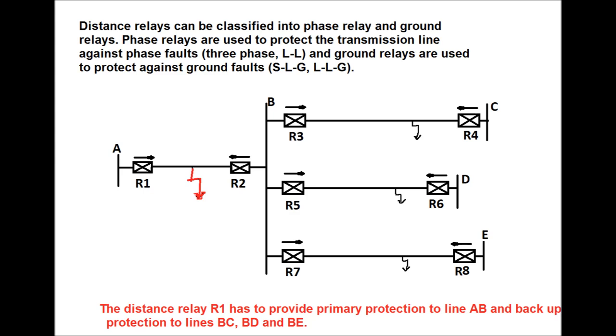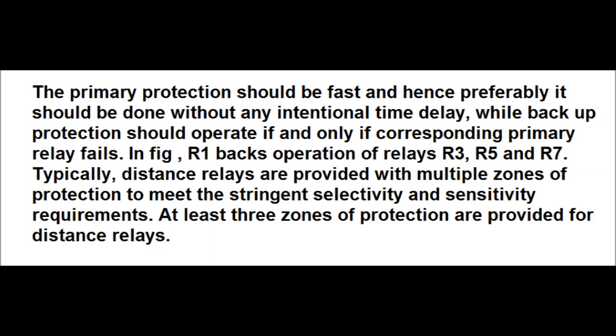From substation B, the shortest line is BD and the longest line is BC; BE is the medium line. Relay R1 has to provide primary protection to line AB as well as backup protection to lines BC, BD, and BE in the forward direction of fault. Primary protection should be fast and preferably done without any intentional time delay, while backup protection should operate only if the corresponding primary relay fails. R1 relay backs up operation of relays R3, R5, and R7. Distance relays are provided with multiple zones of protection to meet stringent selectivity and sensitivity requirements.